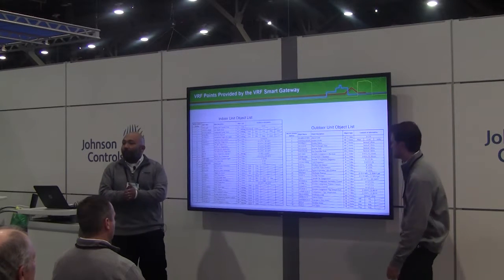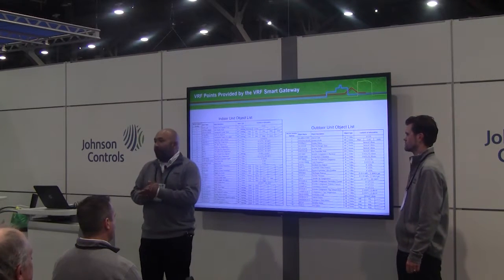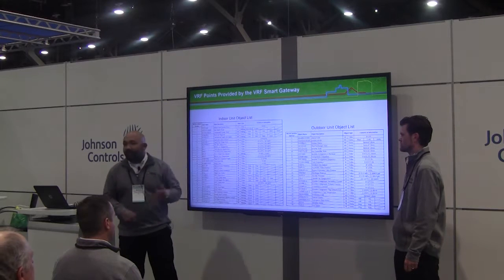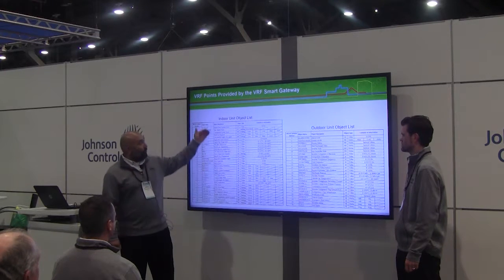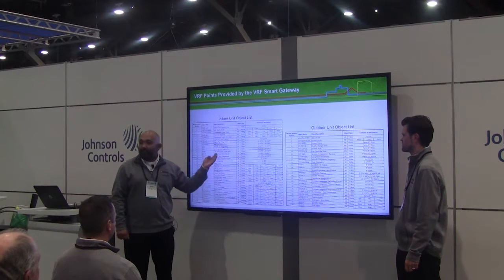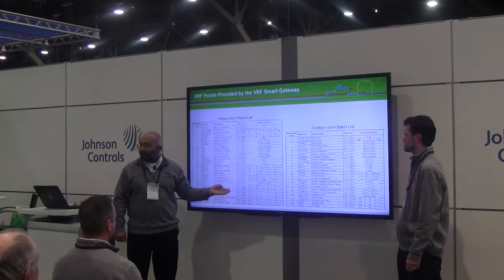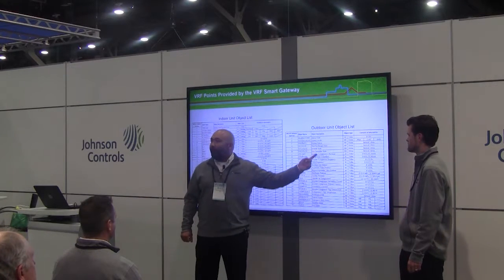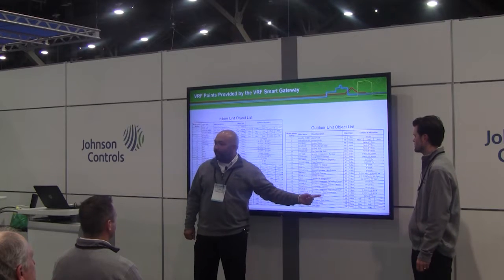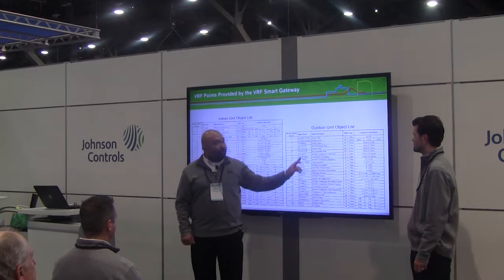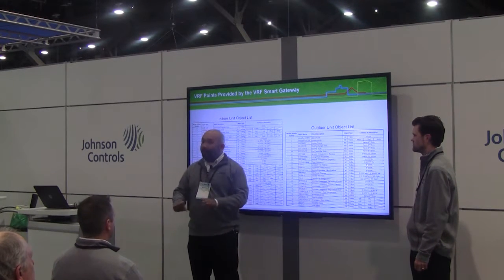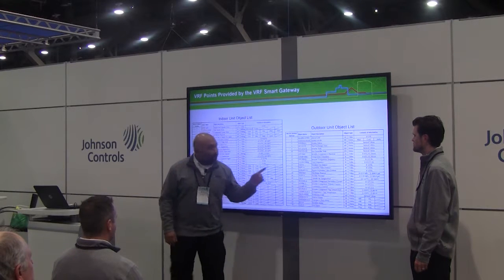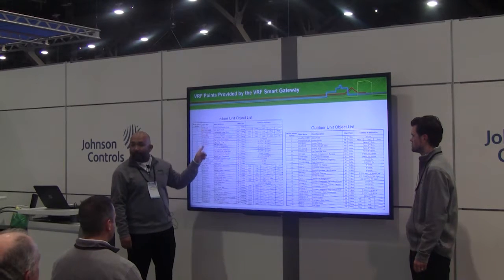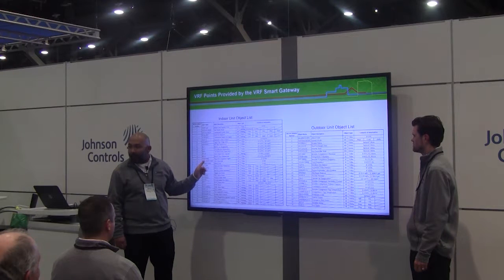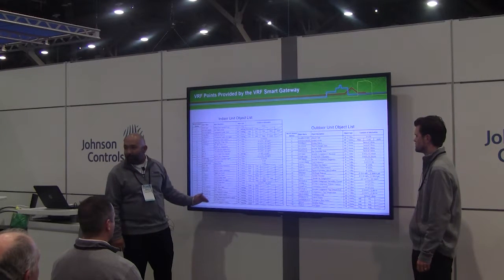Everybody asks for a points list when you're going to install a BACnet system—here's that points list. This is a complete list of the indoor unit items you'll see, and this is a list of the outdoor items you'll get to see. On these point lists is your object name, which will be standard for every single outdoor unit and every single indoor unit—every indoor unit comes with this exact same list.